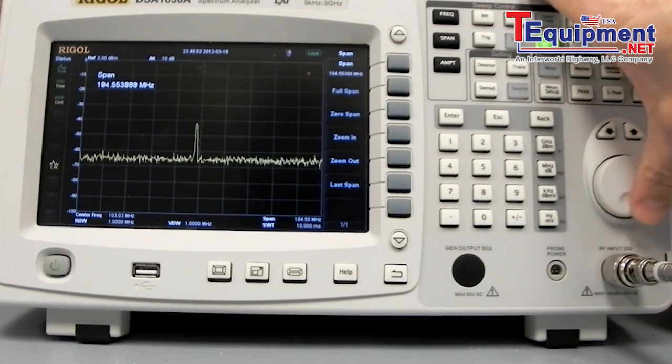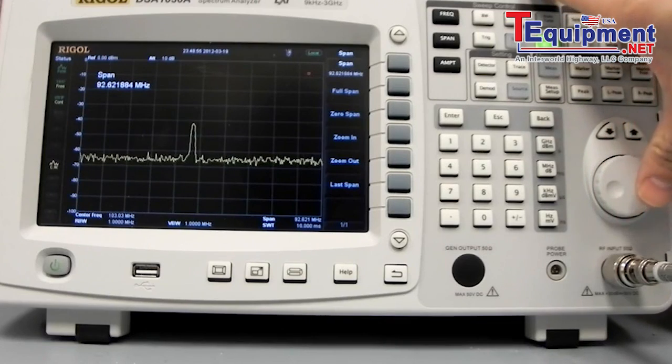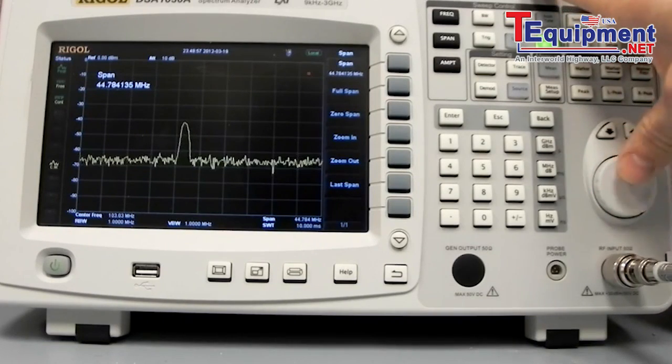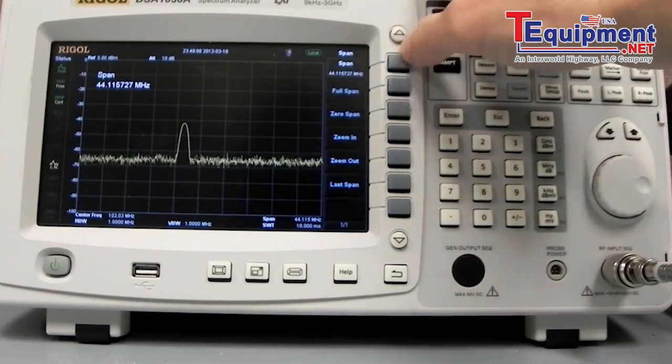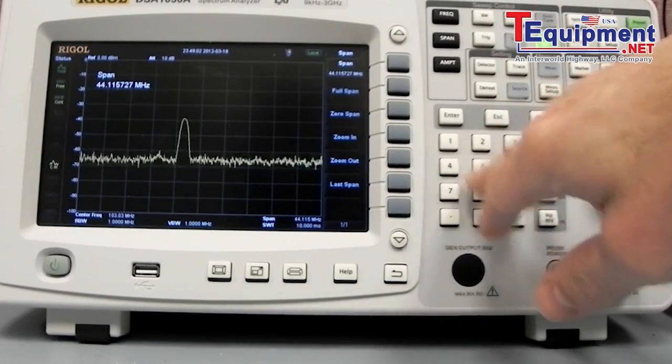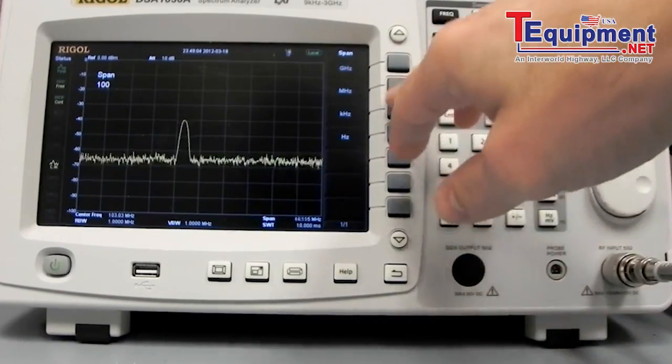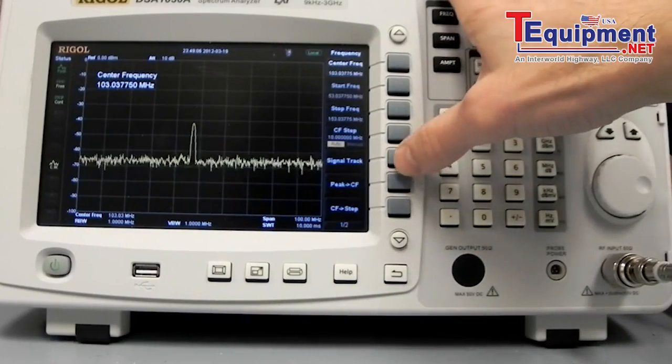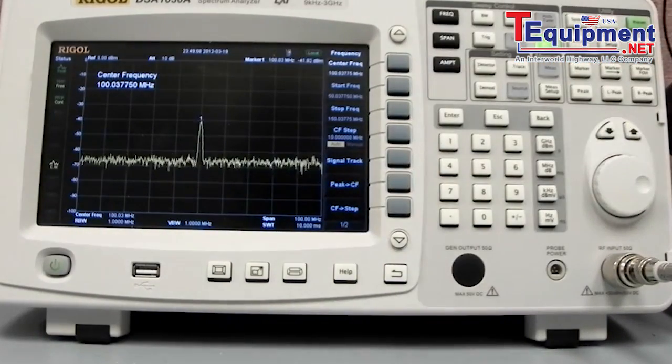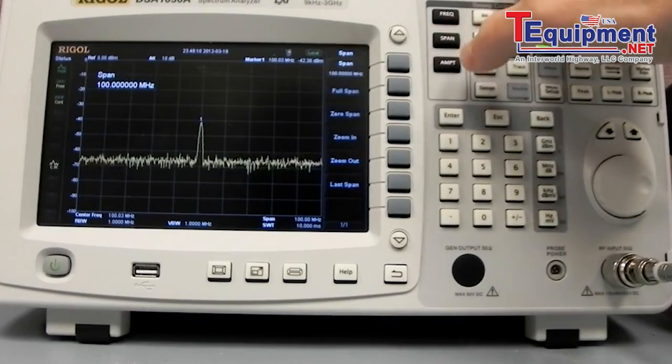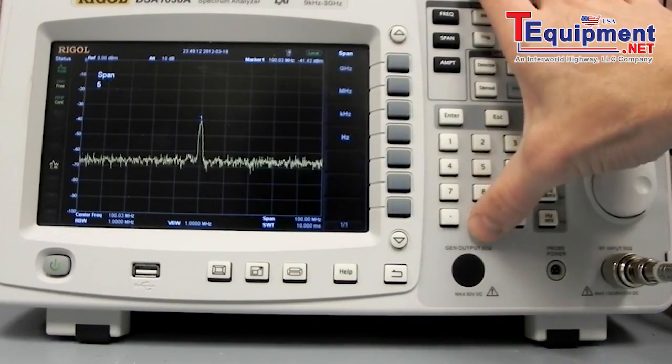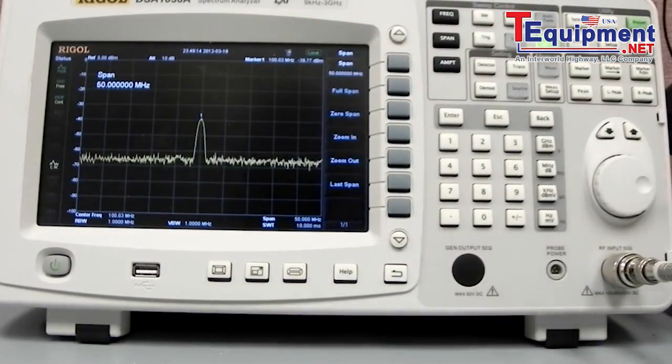Let's zoom in a bit. One way is to adjust the span that way. Another way, you can hit the span and do something like 100 MHz. And we could take to the peak center frequency. And again, let's make the span 50 MHz. We'll just widen it out just a touch.